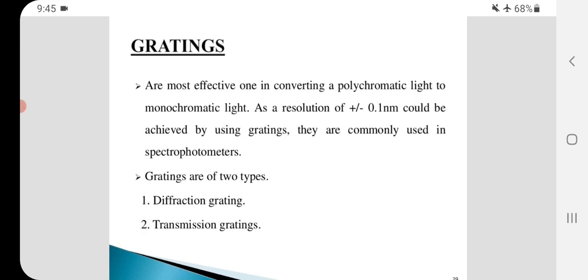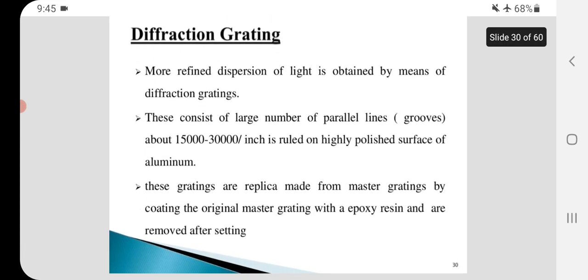Gratings are of two types: diffraction gratings and transmission gratings. Diffraction gratings provide more refined dispersion of light. This consists of a large number of parallel lines about 15,000 to 30,000 per inch ruled on highly polished surface of aluminum.